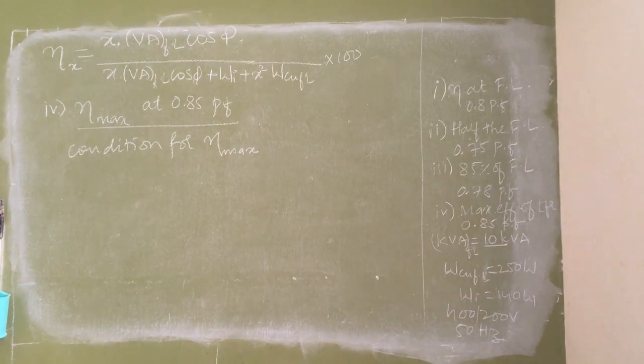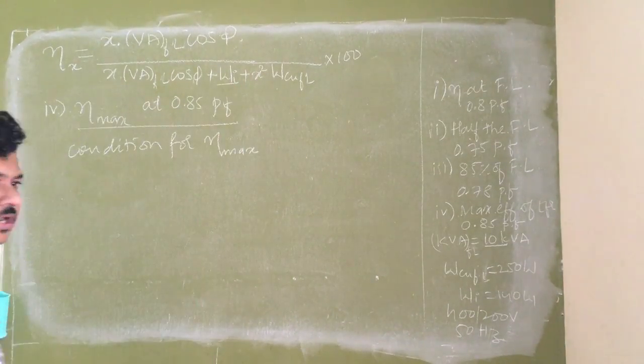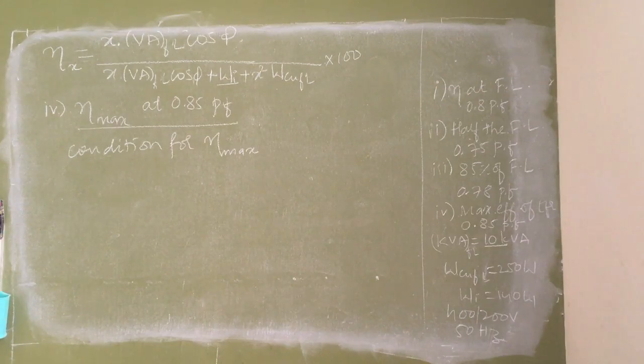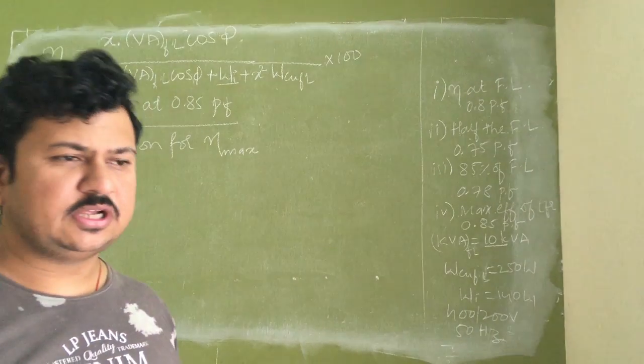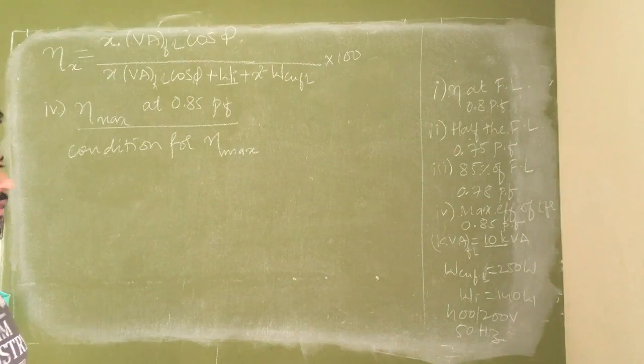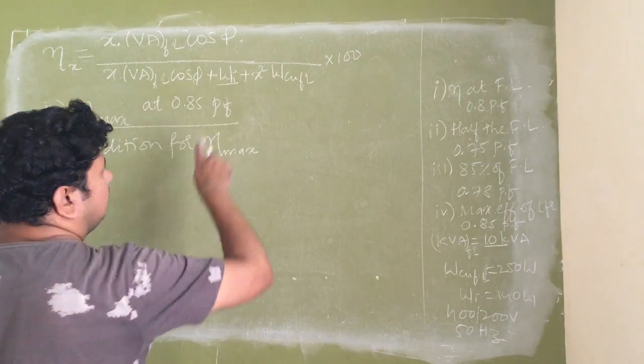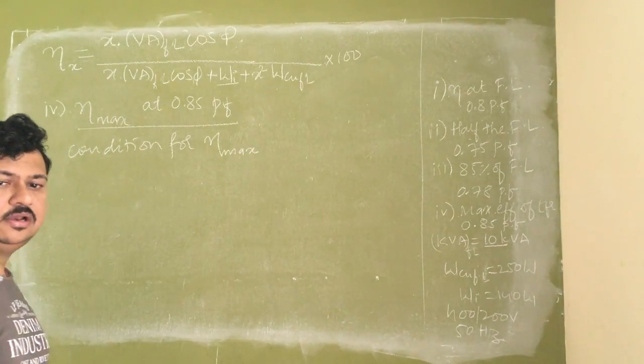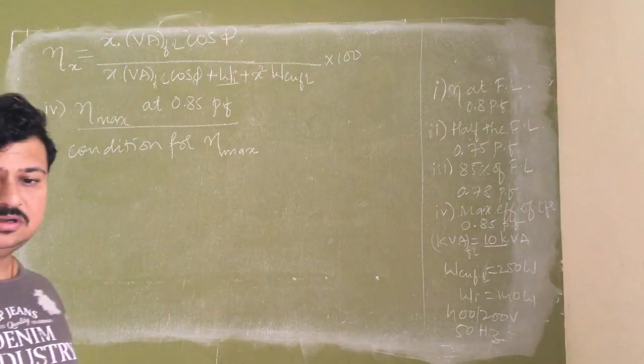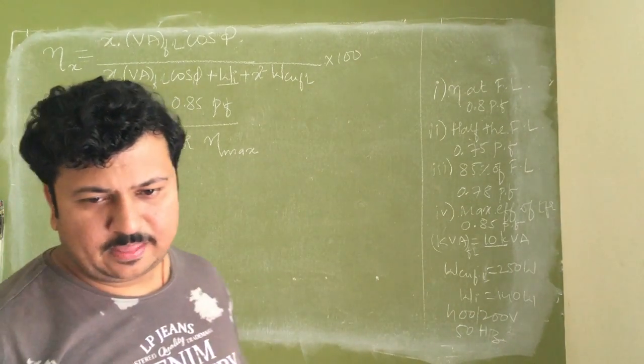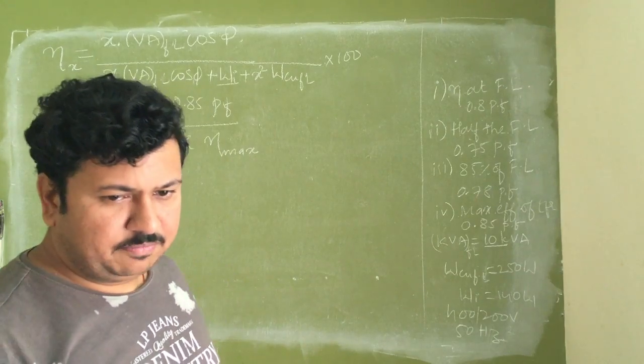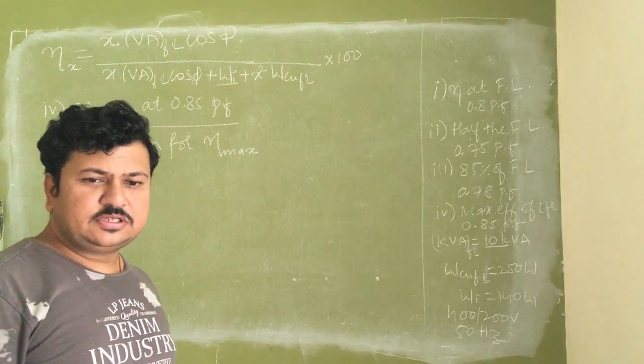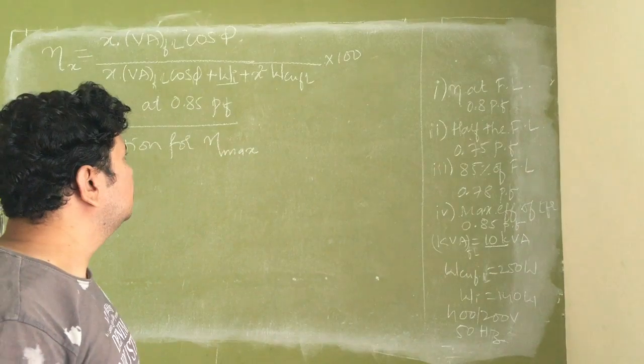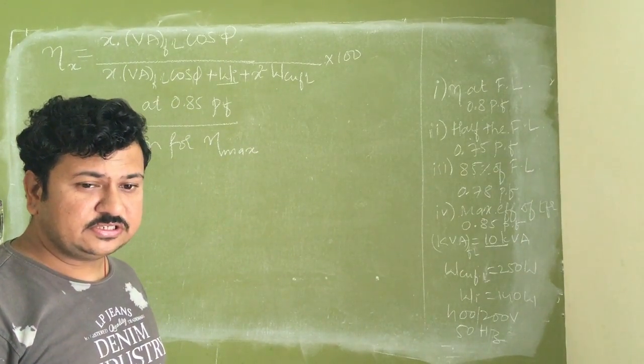Why? Because iron losses are constantly existing the moment the transformer is put into service, whether the transformer is on load or no load. Now, if I take iron losses equal to copper losses, then my iron losses 140 becomes 250, which is not possible. Practically, iron losses will not change with respect to load, but my copper losses can change.